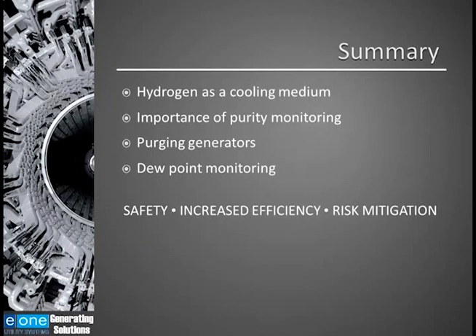All of your monitoring equipment should be tested and calibrated. You should maintain a calibration schedule for your monitoring equipment. I failed to mention this, but the sensors on dew point analyzers need to be recalibrated on a yearly basis. The unfortunate thing is that you can't order a spare sensor, because they begin to age as soon as they're calibrated. So the sensor itself needs to be calibrated every year and used when you get it.